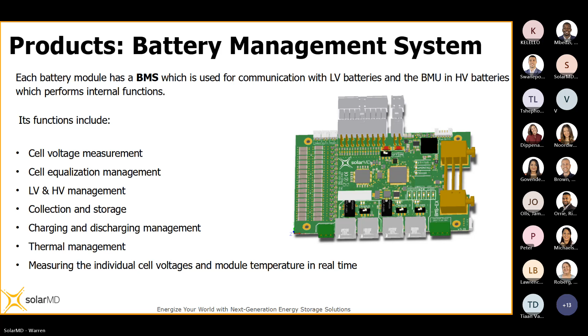It's important to note that the BMS does the measurement and reporting of all the values displayed here - the minimum and maximum cell voltages, the temperatures, and so on. It reports these values, but if you want this information recorded, logged, or graphed somewhere, it's your inverter and its software platform that records this, or the SolarMD logger - possibly both in some cases, as some of our customers use both the inverter brand's portal and our logger simultaneously.